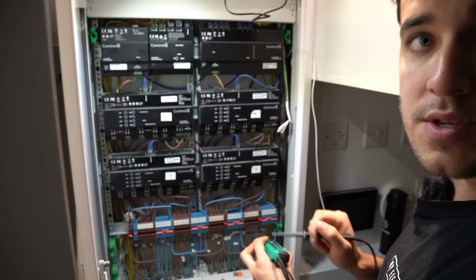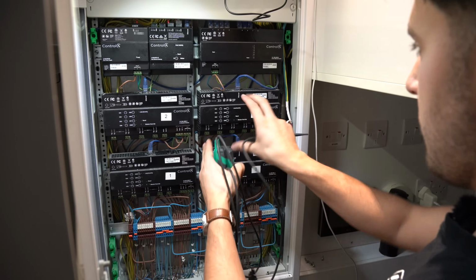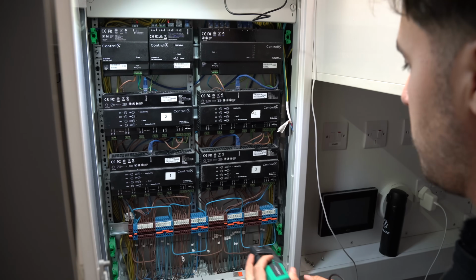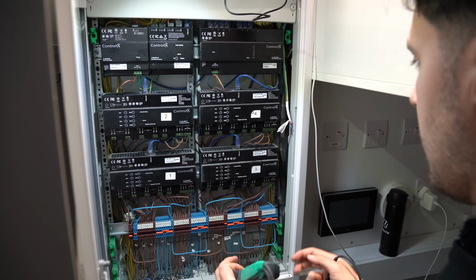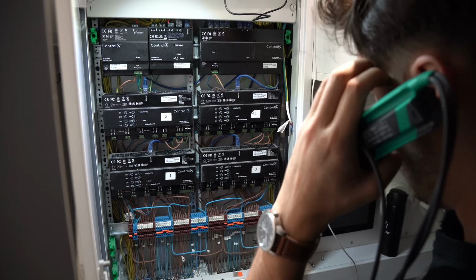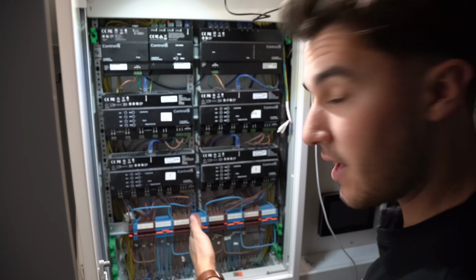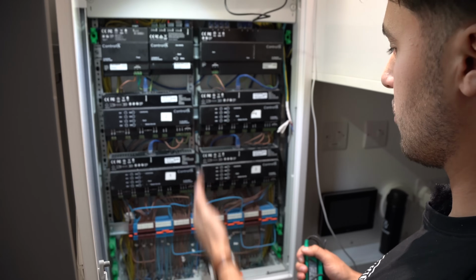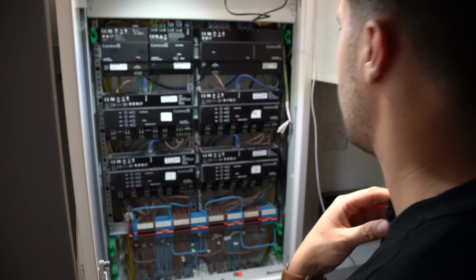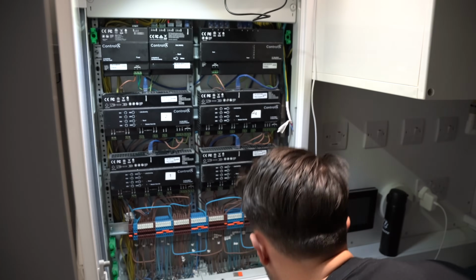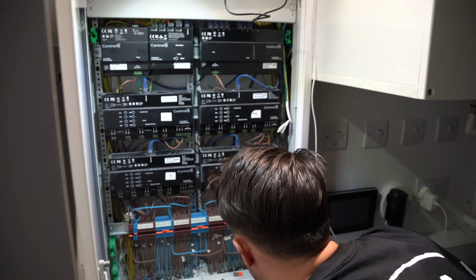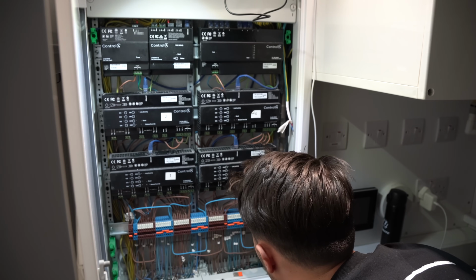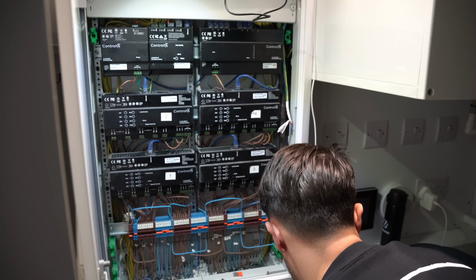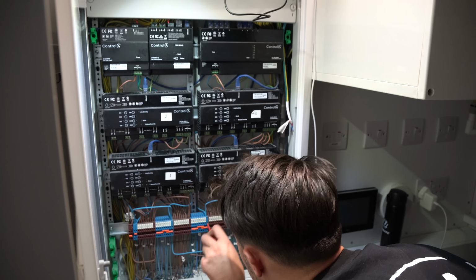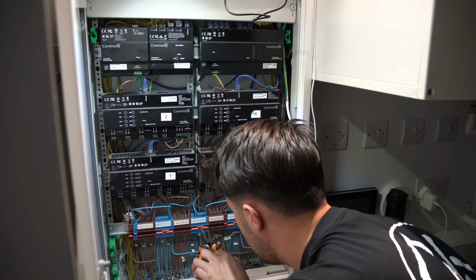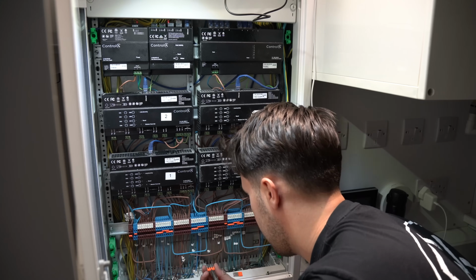What we want to do is separate the neutrals, because I want to put these two dimmer modules on their own RCBO, because at the minute having all of that on there is causing nuisance tripping. I was hoping it was going to be a nice clean split. In a well-designed panel it would be, so that I could just chop it there, that half, but it looks like it's not going to be that simple. We'll actually have to manually trace a lot of these out, I think. Yeah, so that is the common down neutral for all of them. So I reckon if I was to split this off, let's say here, this little jumper bar, out and move that long one.